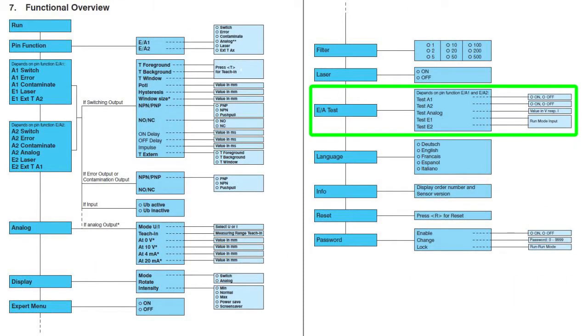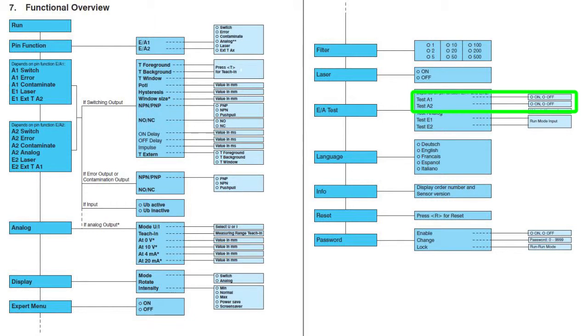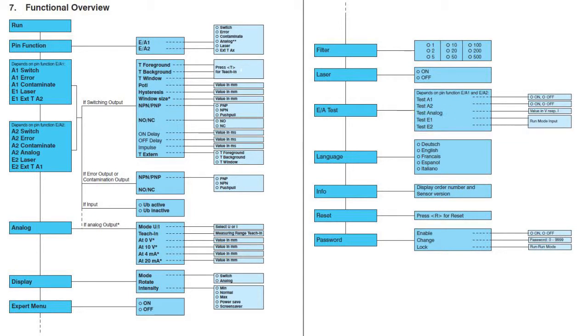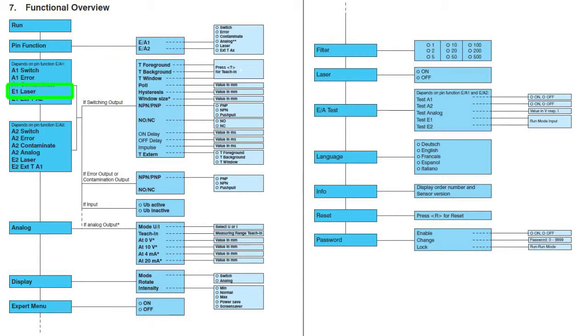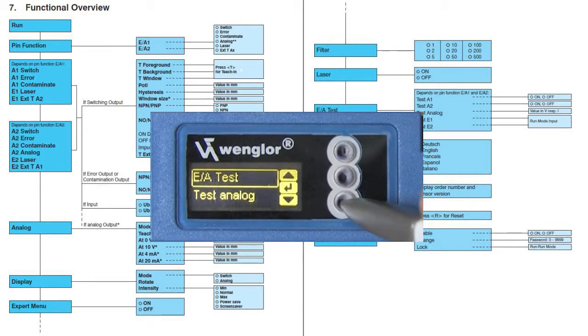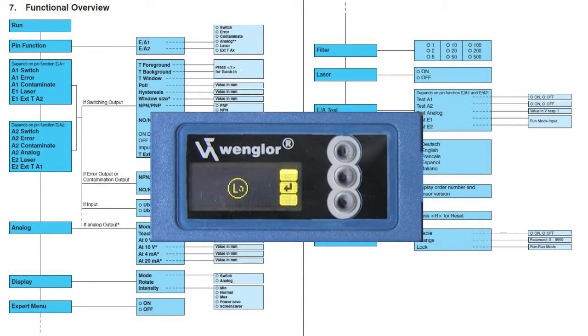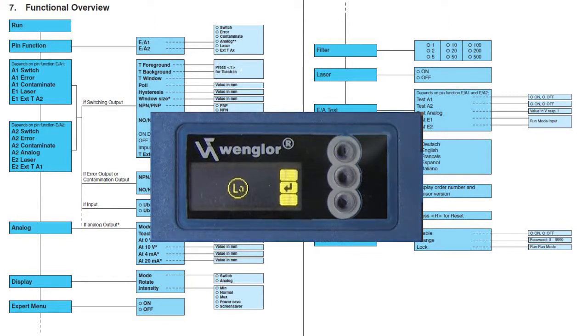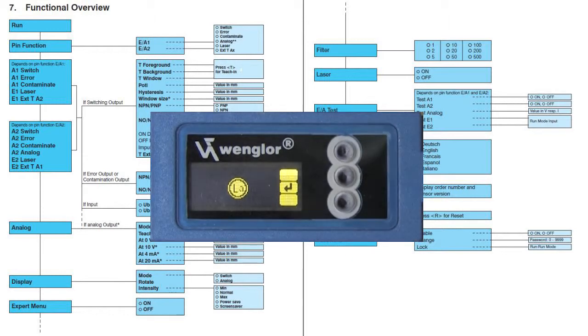The test menu is awesome. You can force individual output pins high or low, force an analog output to any value you want, either current or voltage depending upon how you set the pin up, and you can test any pins that are set up as inputs. What you see here depends on how you have your pins set up back in this menu. Right now my sensor is set up with A1 as an input and A2 as an analog output. To test the input pin, I drop into that menu, apply a voltage to the input and the little pin bubble lights up. This is a great way to set up, calibrate and test your system.